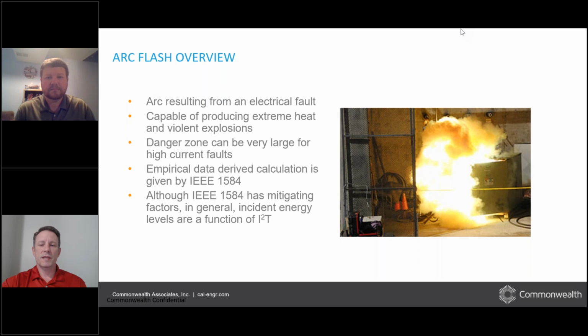The danger zone from these can be anywhere from a couple of feet to a couple of dozen feet, depending on how much fault current there is. Most of the calculation for these danger zones are from IEEE 1584. In general, the incident energy is a function of current and time, so I squared T.